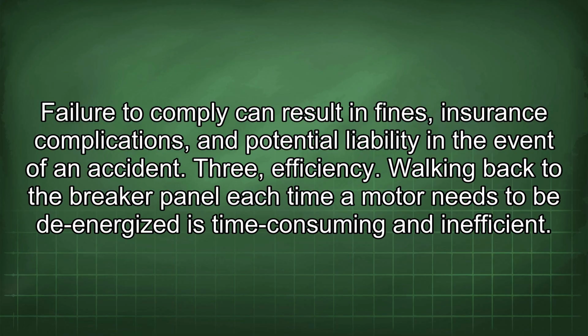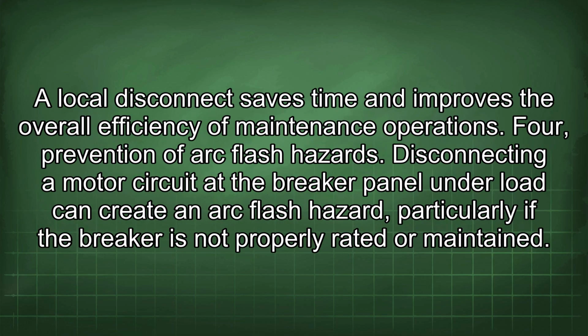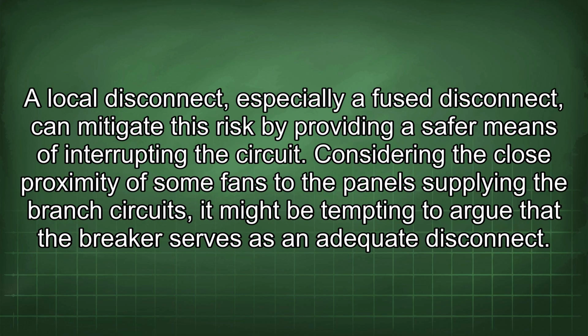3. Efficiency. Walking back to the breaker panel each time a motor needs to be de-energized is time-consuming and inefficient. A local disconnect saves time and improves the overall efficiency of maintenance operations. 4. Prevention of arc flash hazards. Disconnecting a motor circuit at the breaker panel under load can create an arc flash hazard, particularly if the breaker is not properly rated or maintained. A local disconnect, especially a fused disconnect, can mitigate this risk by providing a safer means of interrupting the circuit.